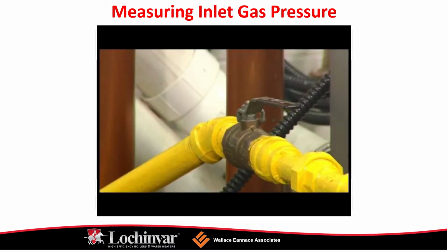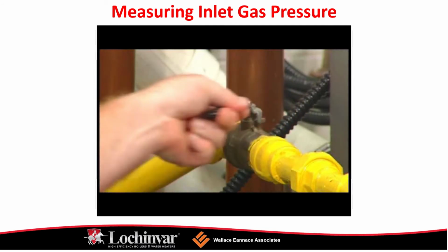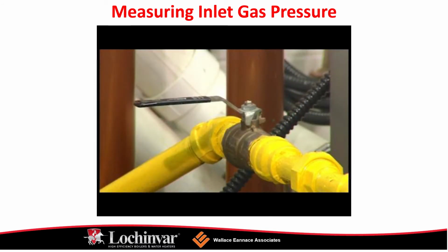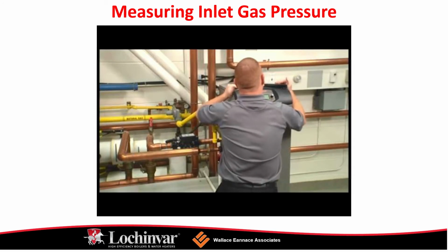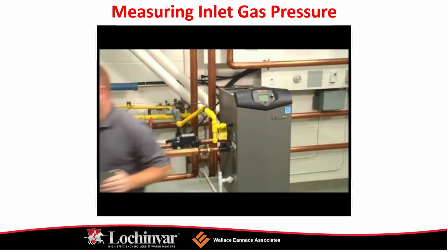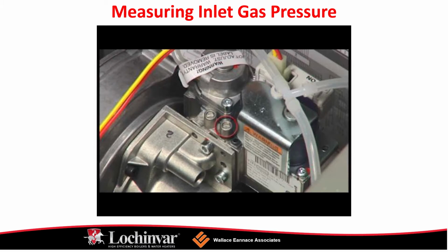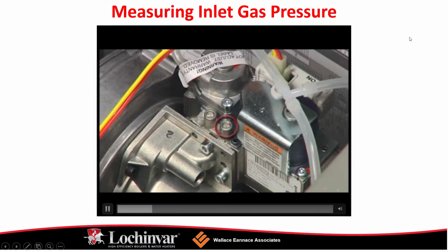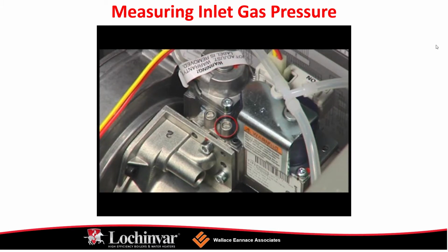Installing gas, for natural gas models, we need a maximum 14-inch water column, a minimum of 4-inch water column. And if we're talking about liquid propane, we're talking 14-inch water column again, but the minimum will be the 8-inch on that. Beware of sharp pressure drop on the inlet pressure when the unit starts. How to measure gas pressure. Let's take a look.